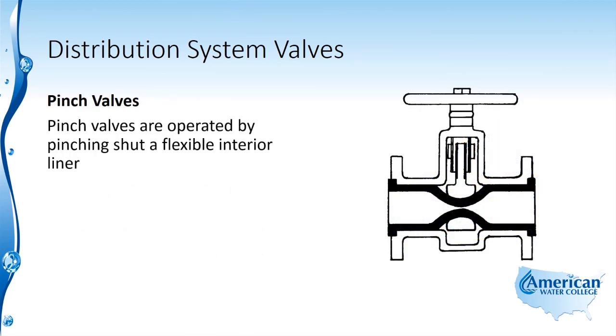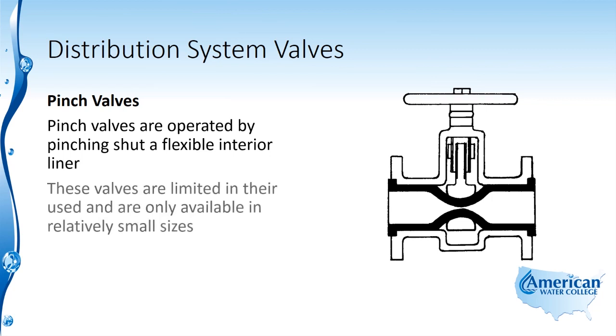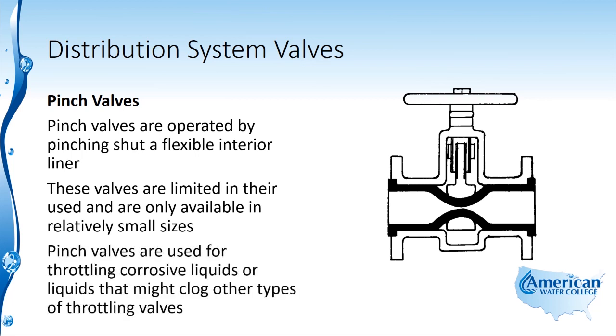Pinch valves are operated by pinching shut a flexible interior liner. These valves are limited in their use and are only available in relatively small sizes. Pinch valves are used for throttling corrosive liquids or liquids that might clog other types of throttling valves.